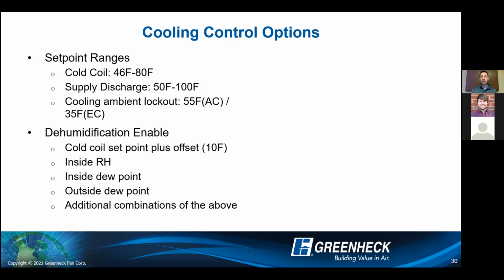And then from a cooling ambient lockout, if we think back to those condenser fans, if it's all AC, so if you select no EC condenser fans, 55 degrees is really going to be that ambient lockout. Now, if you have that lead EC or all EC motor selected on the condensing fans, currently right now we can go down to 35 degrees if that's the case. If you have certain applications where, in Georgia, you probably won't need to go much lower than that. But if you're working on applications where maybe it's somewhere else that they need low ambient cooling, we can always look at that via special design. But again, work with Holden, they'll work with us, and we can look internally with our performance on the refrigeration side of things.